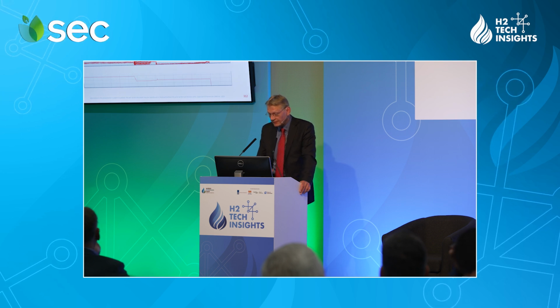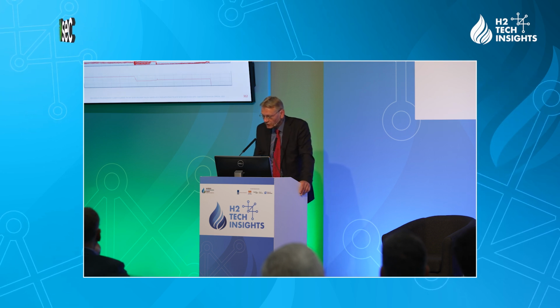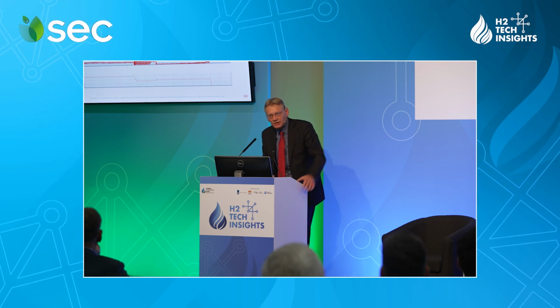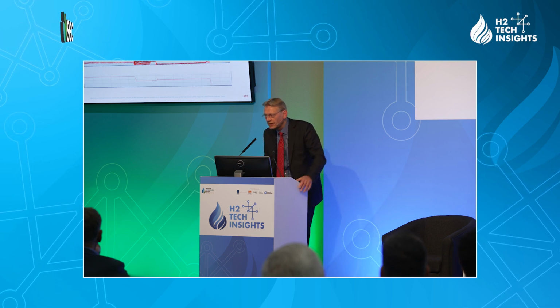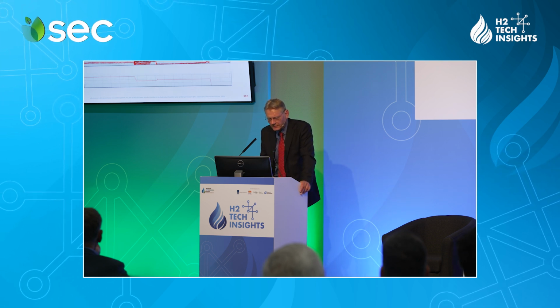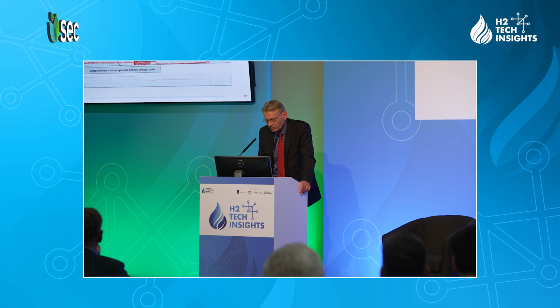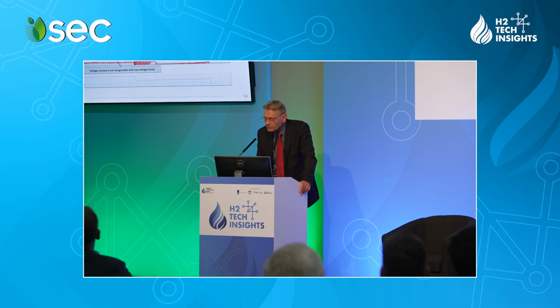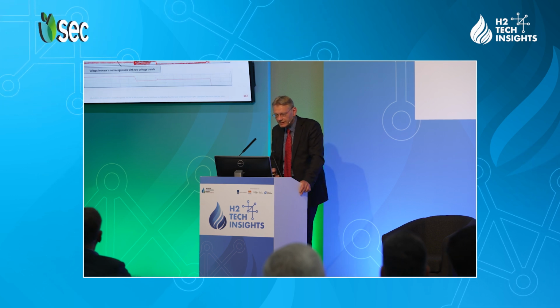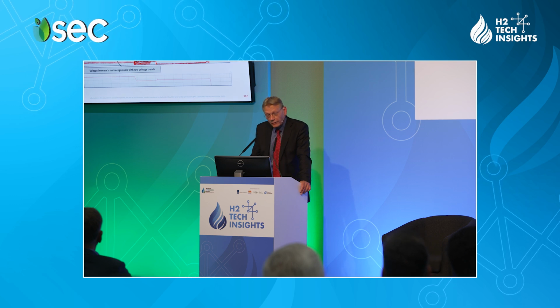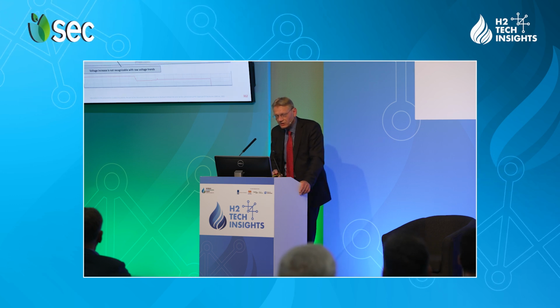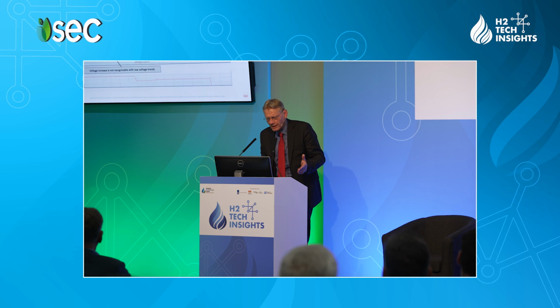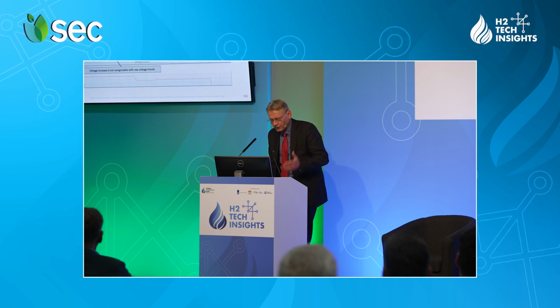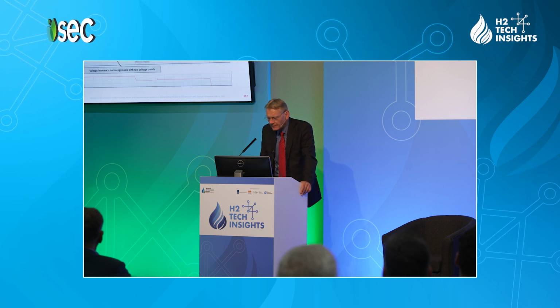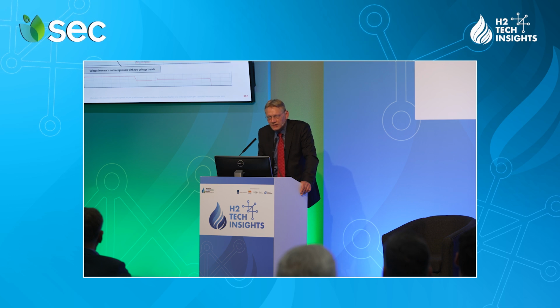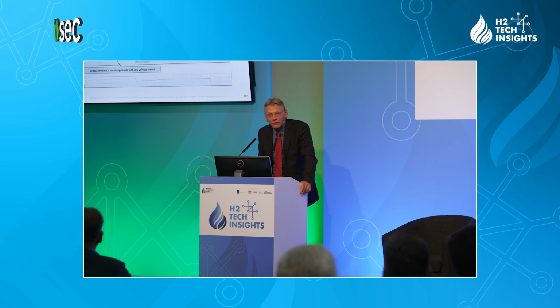Looking at the trends, it's even more impressive. Inside all the cell voltages, the black sheep is hidden. You see at the bottom the current and then all the cell voltage trends of one electrolyzer. There is a voltage increase. With the residuals, so difference between measured and predicted, you can see it right away. If I remove some of the cells, some of the trends, you can also see it with the raw voltage, but you cannot put an alarm on it. With the strategy of the residuals, you can already alarm an increase of 10 to 20 millivolt of abnormal behavior.